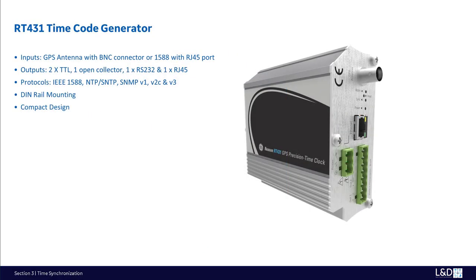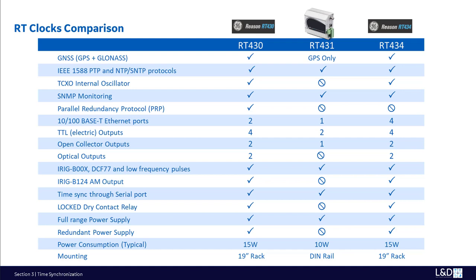The RT431 timecode generator is a compact GPS-based clock designed to be installed on a DIN rail that supports electrical DC level shift time signal, serial datagram, network time protocol NTP, simple network time protocol SNTP, and IEEE 1588 V2 precision time protocol PTP. When configured as a PTP ordinary clock, slave, RT431 also works as a transceiver from PTP to IRIG-B serial or pulse time codes, enabling the use of PTP on legacy IEDs that do not support this protocol. Here, you can pause the video to see the feature comparison of the 3 clocks RT430, RT431, and RT434.